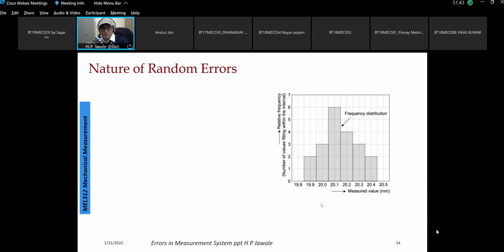Let us understand now how the random error is going to behave. First of all, we must understand what the result is. When a reading is found out, the random error is nothing but the difference between the mean value and the measured value. It is quantified by taking the difference from the mean that would result from an infinite number of measurements, which means a sufficiently large number of readings for the same input, of the same measurand carried out under repeatability conditions. I think the meaning of repeatability will be defined in the next class.